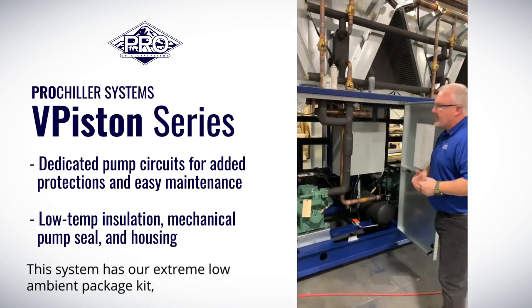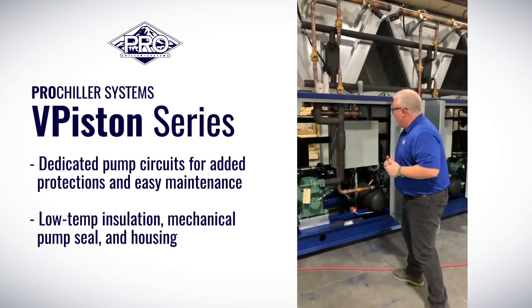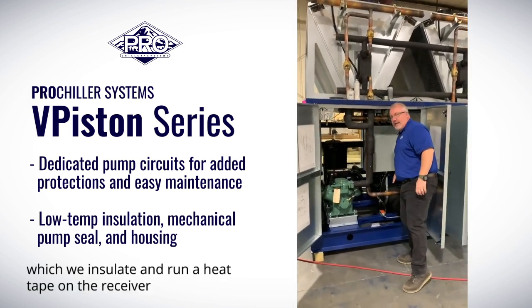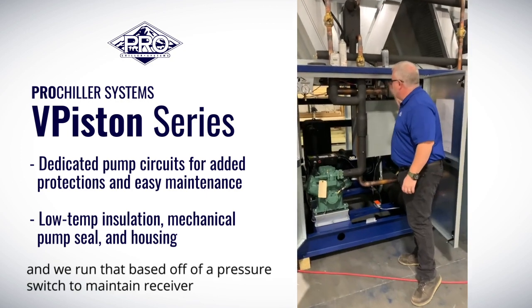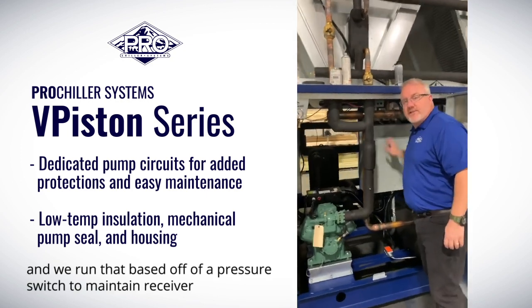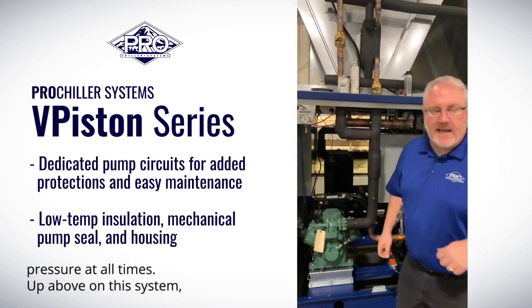This system has our extreme low ambient package kit, which we insulate and run a heat tape on the receiver, and we run that based off of a pressure switch to maintain receiver pressure at all times.